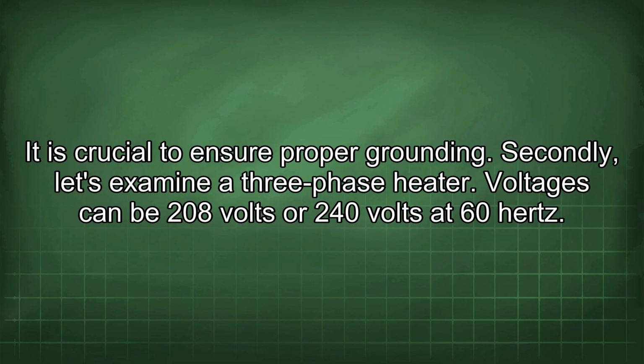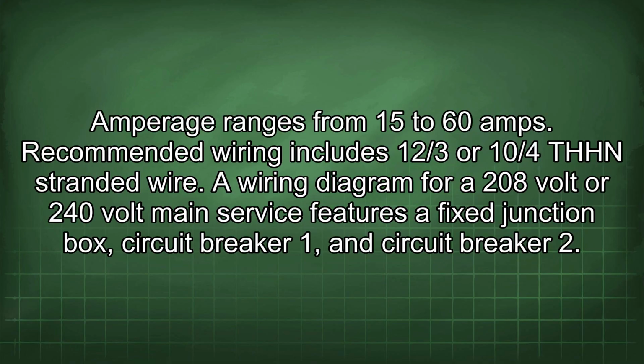Secondly, let's examine a three-phase heater. Voltages can be 208 volts or 240 volts at 60 Hz. Amperage ranges from 15 to 60 amps. Recommended wiring includes 12/3 or 10/4 THHN stranded wire.